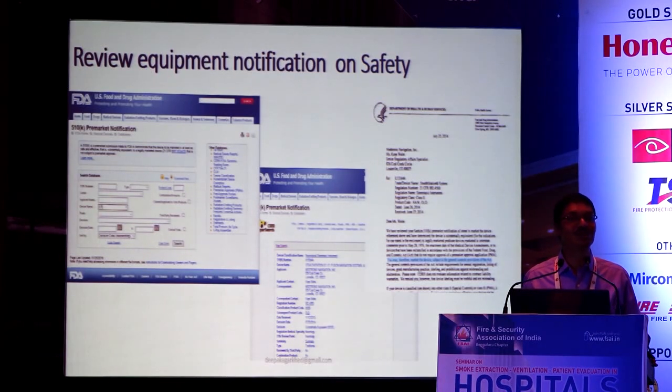In fact, I introduced this standard in the 4th edition NABH for recall of medical equipment. So at least those 500 plus NABH accredited hospitals can ensure that equipment is checked on a regular basis, recalls are notified, and we take it out of clinical usage. Unfortunately, the service providers don't voluntarily come and say there is a recall.